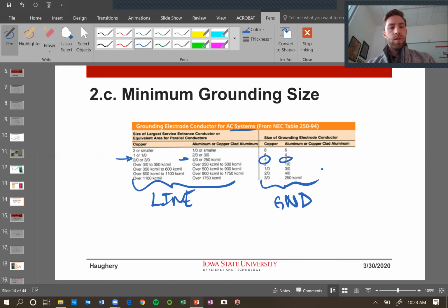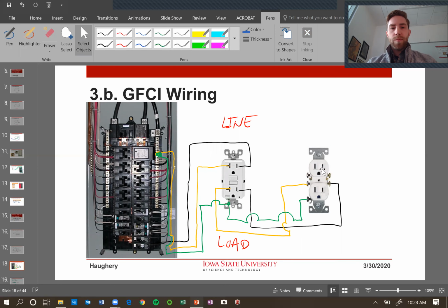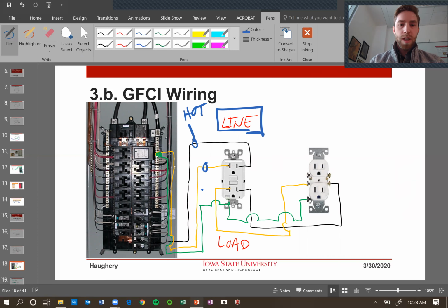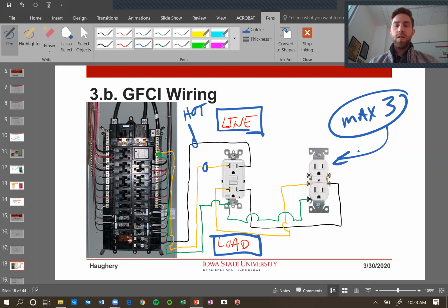If we looked at GFCI wiring, we notice that we have our line, our hot, or our line from our panel feeding into the line, as well as the neutral from the panel feeding into our line. It's very important when you have a GFCI that the input is the line, and then anything past the GFCI that you want to protect with that GFCI, you come out of the load. And I can have up to 3 of these receptacles after a GFCI to be protected. More than 3, I have to get a second GFCI.